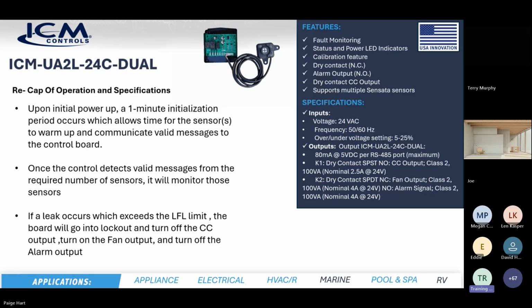So they want you to be able to see the LED light when everything is good, so that you can peek into the box and say, am I good? Oh yeah, I see a light. Say it's dark outside, peek in the box, you can see a light, you're good. If you get a leak and it goes into lockout, then that light goes out. So if you don't see that LED illuminated anymore, you're in lockout. You gotta mitigate. You got a problem with the leak. You gotta fix that leak.